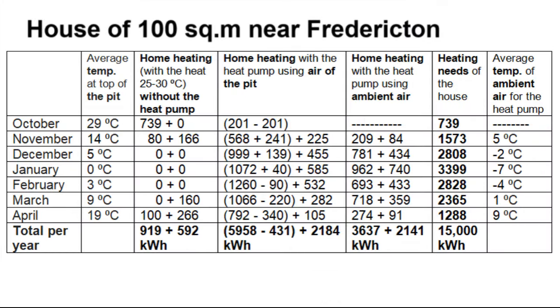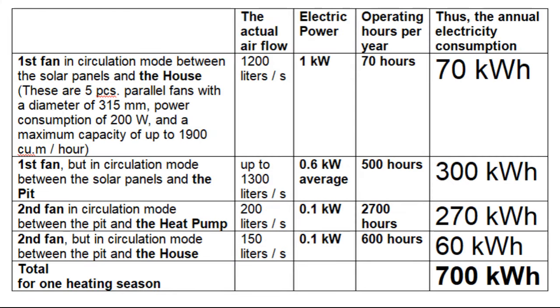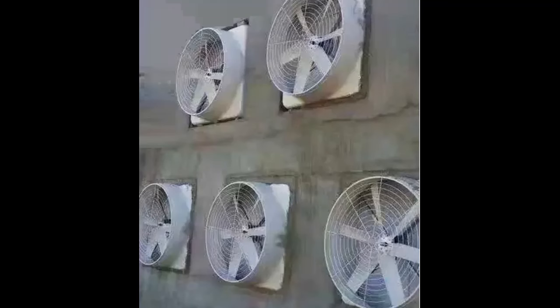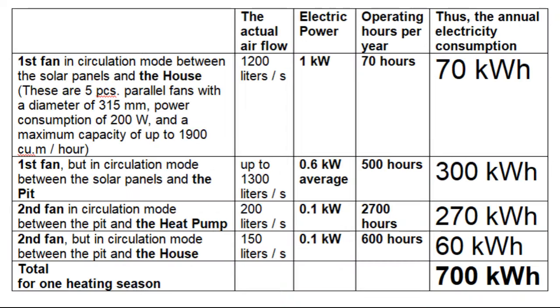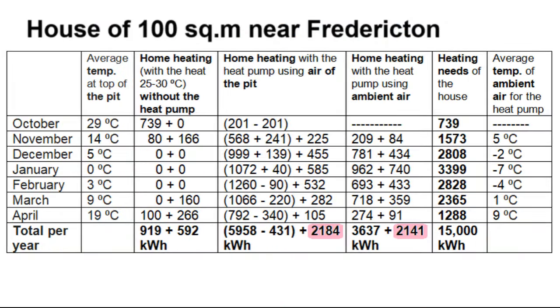This graph was also used to calculate the electrical component based on ambient temperature. This is my attempt to estimate the power consumption of those two fans. We see that the first fan is five parallel fans, and thermostats turn off a certain number of the fans if the temperature difference between these points is less than 10 degrees.